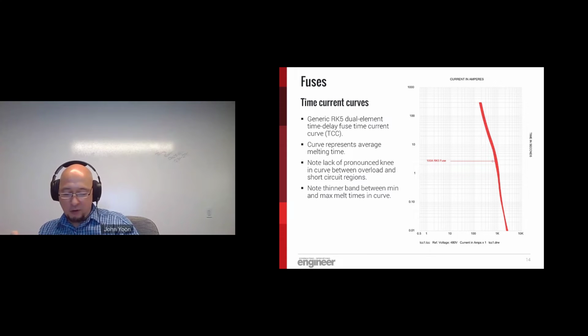And on these time current curves, time in seconds is always on the vertical y-axis and current in amps is on the horizontal x-axis. In this particular time current curve, this is for a generic 100 amp fuse. The red band that you see here represents the minimum and maximum melt times for the elements in that fuse. Everything to the left of that curve is normal operating conditions and the fuse will not open. Once you hit the red band or go to the right of it, the fuse will open the circuit.